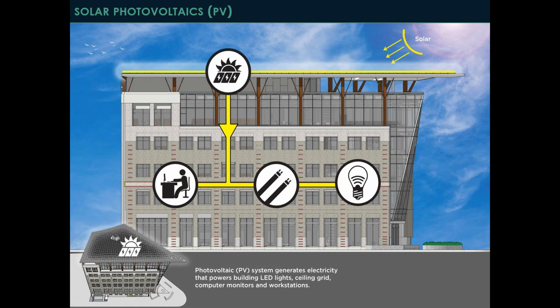So we had to be smart about it. The PV system is a little different than most PV systems in that it generates DC power—that's not unusual. What is unusual is we use that DC power throughout the building. Most buildings take that DC power, run it through inverters and rectifiers, change it to AC power, and then use the AC power because that's what most buildings need.